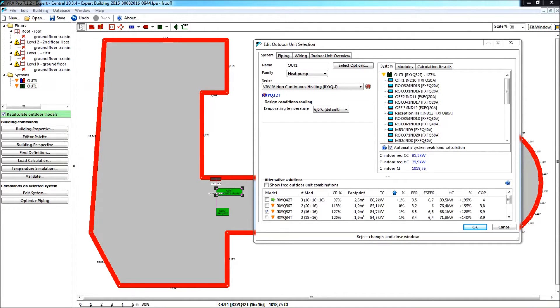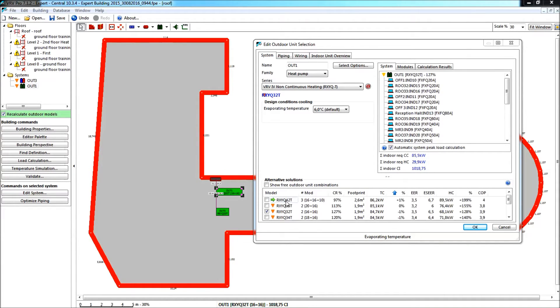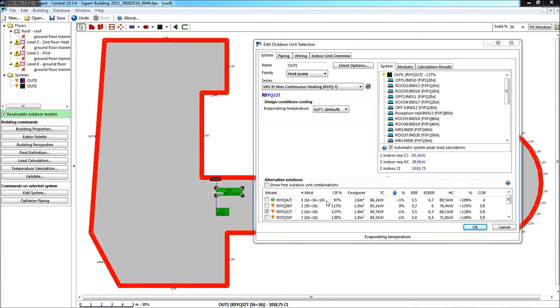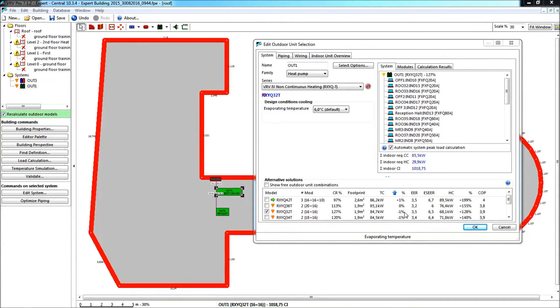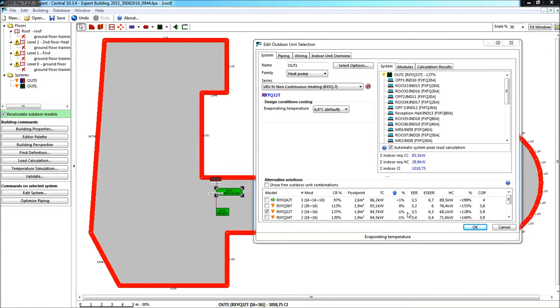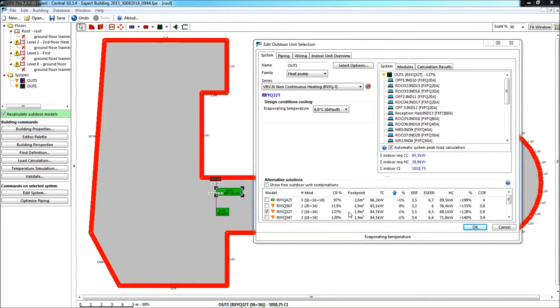Now you see that I did a manual resize, a manual resize versus the proposed unit that covers all of the load. You see, I have an excess of 1%, but I have a 3-module outdoor unit here. Now I prefer to use a 2-module outdoor unit by resizing this unit, knowing that this would result in a capacity shortage of only 1%, but I'm gladly to accept this. I have also a wonderful connection ratio of 127% on that unit, so definitely, personally, I would go for this unit.